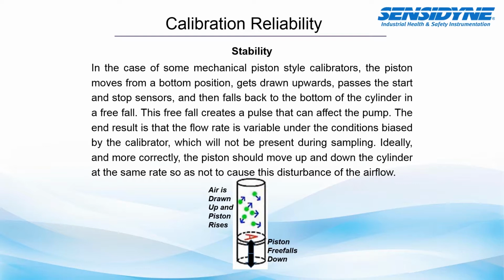So what's happening is you'll actually see a different flow rate when the calibrator is connected to the pump with these piston-style calibrators. Ideally and more correctly, the piston should move up and down the cylinder at the same flow rate so as not to cause a disturbance of the airflow.